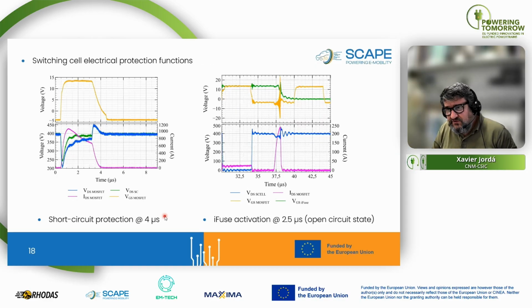The protections: you can see here the short circuit protection. We introduced a short circuit in the switching cell with a maximum current up to 1000 amps, and this short circuit is correctly shut off by the desaturation protection of the gate driver in less than 4 microseconds.